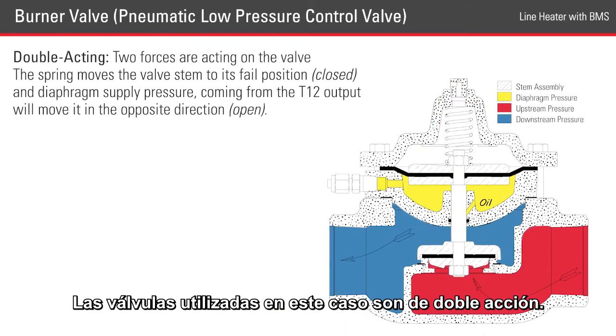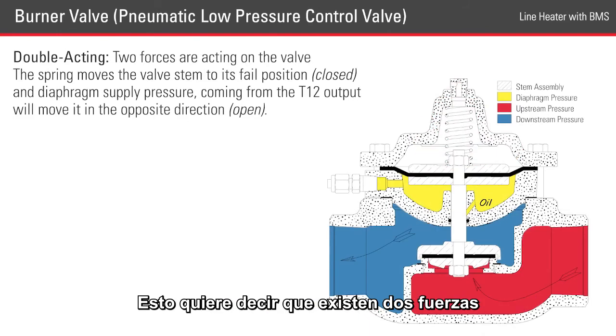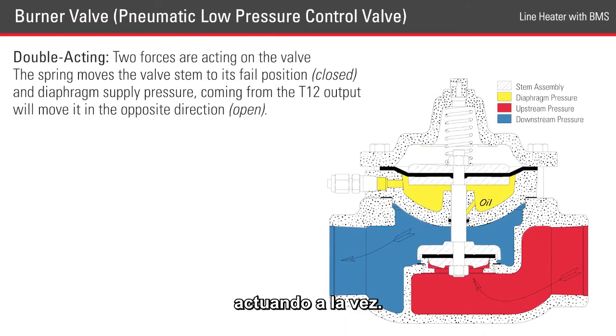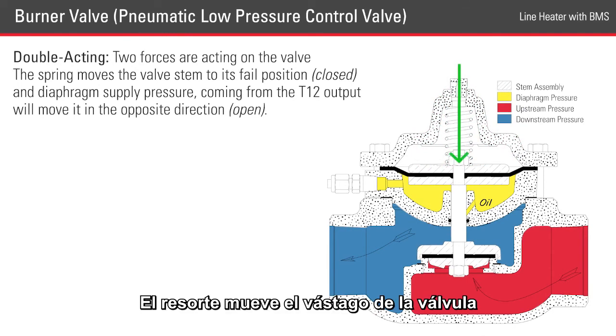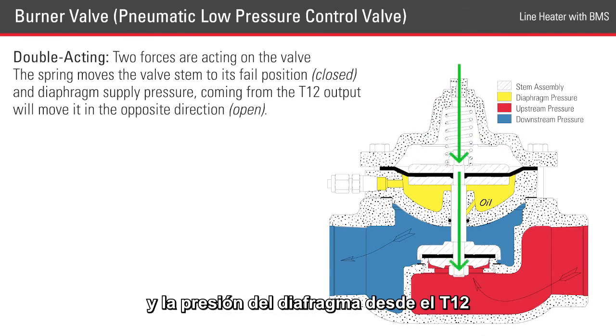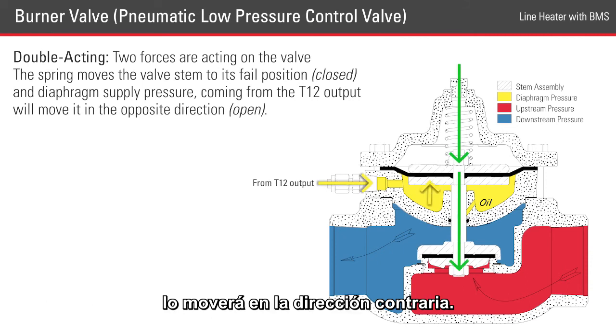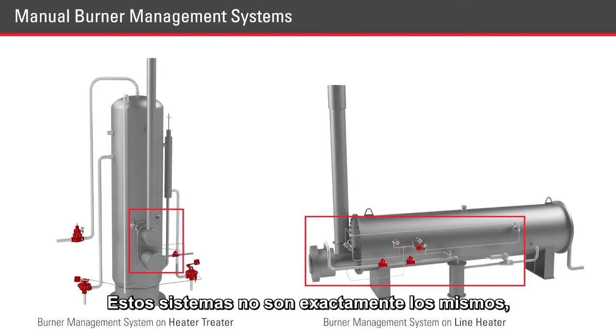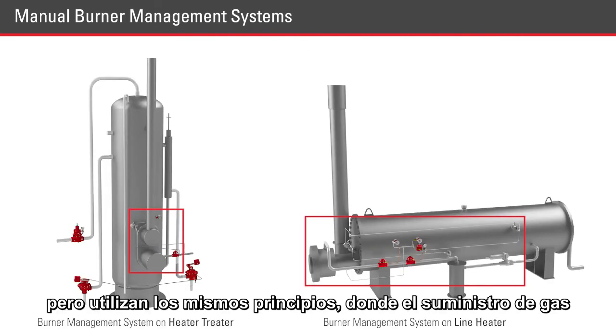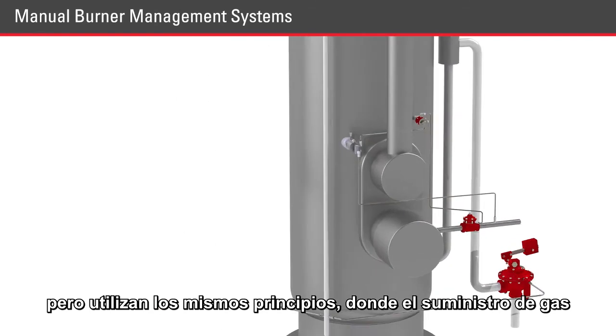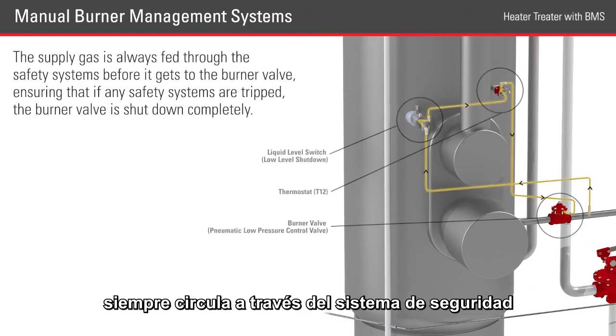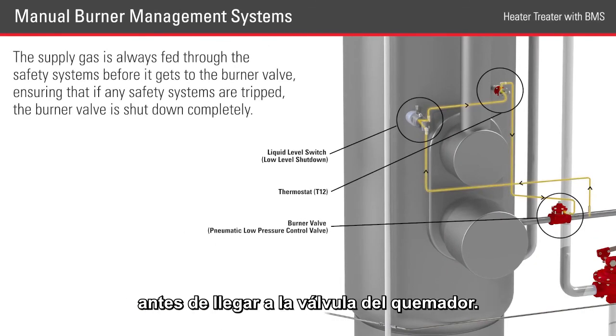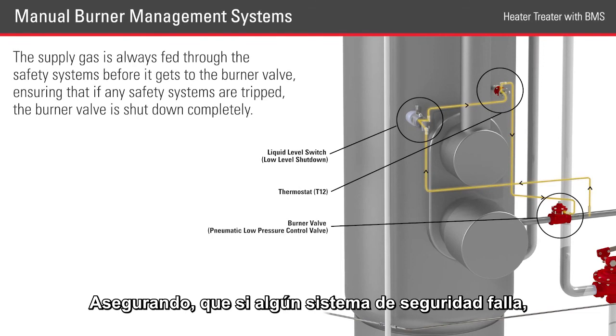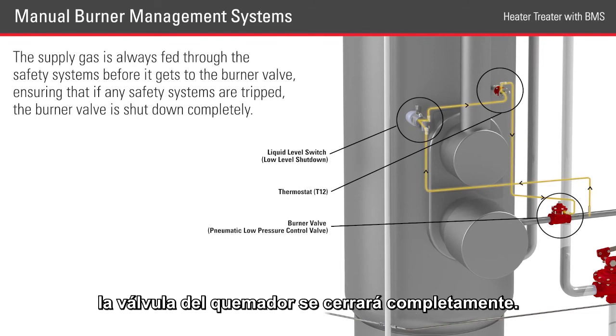The valves used in this application are double acting, meaning that there are two forces acting on the valve. The spring moves the valve stem into the fail position, and the diaphragm supply pressure coming from the T12 will move it in the opposite direction. These systems are not exactly the same, but they will use the same principles: the supply gas is always fed through the safety systems before it gets to the burner valve, ensuring that if any safety systems are tripped, the burner valve is shut down completely.